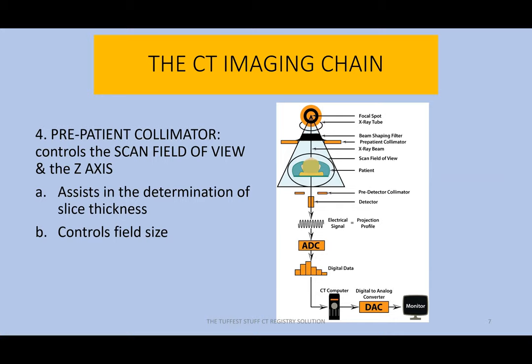That's what we're talking about with the pre-patient collimator — a pretty important piece of equipment. Because with it, we're going to limit the field being exposed to radiation. By doing that, we're going to limit the amount of scatter produced, and by doing that, we're going to severely limit the clouding over of details that occurs when scatter radiation impacts an image.